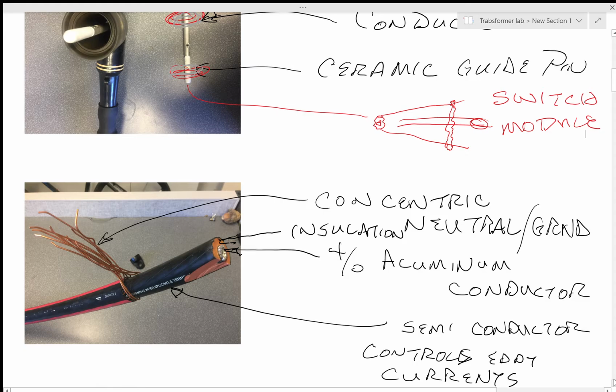Here's the wire that this elbow is on. You've got a concentric neutral that just coils up, wraps up into a ground, and goes on to wherever the ground is in that system. You have a semicon right here. This black stuff right here is a semiconductor. Basically, it controls eddy currents. Eddy currents are currents that come out 90 degrees, perpendicular to the magnetic field. So this semiconductor basically controls the magnetic field and the eddy currents and keeps them inside the insulation and doesn't let them get outside where they could cause damage. You have this orange piece right here, that is the insulator. And then you have a stranded aluminum conductor in there.